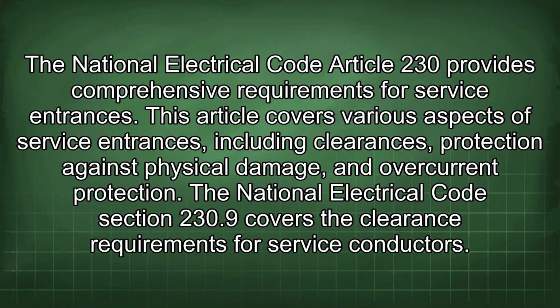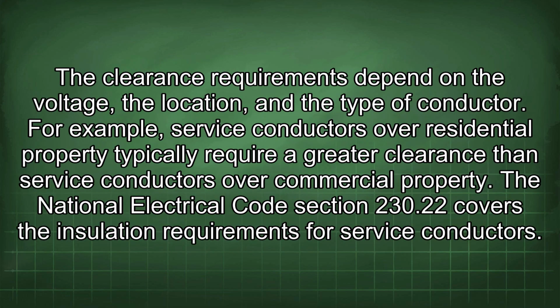The National Electrical Code Article 230 provides comprehensive requirements for service entrances. This article covers various aspects of service entrances, including clearances, protection against physical damage, and overcurrent protection. The National Electrical Code Section 230.9 covers the clearance requirements for service conductors. The clearance requirements depend on the voltage, the location, and the type of conductor. For example, service conductors over residential property typically require a greater clearance than service conductors over commercial property.